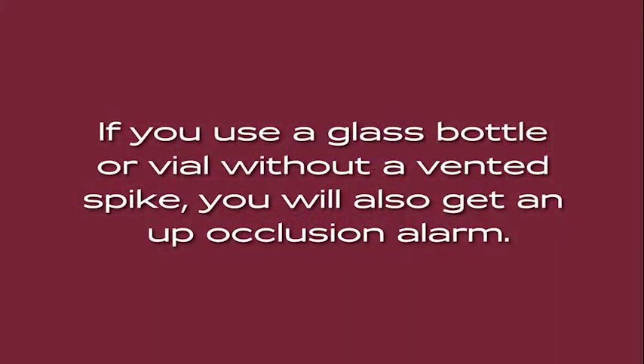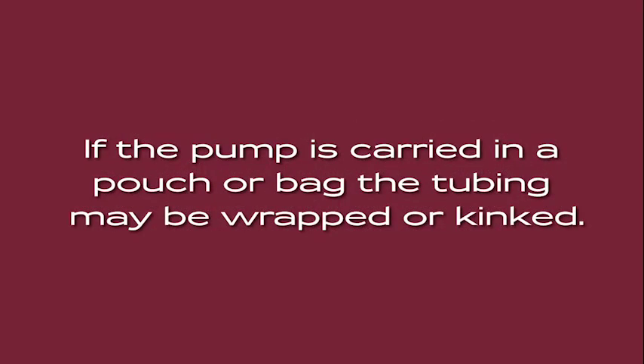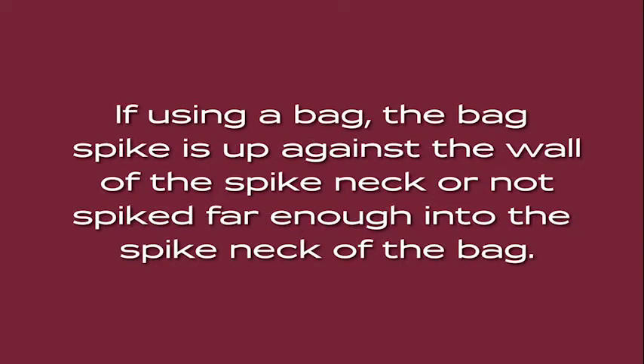If you use a glass bottle or vial without a vented spike, you will also get an up occlusion alarm. If the pump is carried in a pouch or bag, the tubing may be wrapped or kinked. If using a bag, the bag spike is up against the wall of the spike neck, or not spiked far enough into the spike neck of the bag.